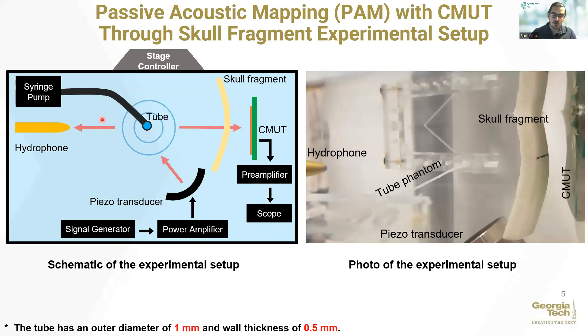To test the capabilities of CMUT for passive acoustic imaging in transcranial applications, the experiment diagram on the left was performed. Initially, the piezo transducer aligned the phantom tube with pulse-echo measurements. After the CMUT array was inserted into the water tank and its natural focus covered the tube phantom, a hydrophone was placed in the setup. Finally, the skull sample from the parietal region, which has around 8 mm thickness, was placed in front of the CMUT array. Water and microbubbles were circulated through the tube phantom. The piezoelectric transducer was used as a transmitter and the CMUT was used as a receiver with a bias of 50 volts. The received signal was amplified by 20 dB and recorded by oscilloscope. The experiment setup photo can be seen in the picture on the right.